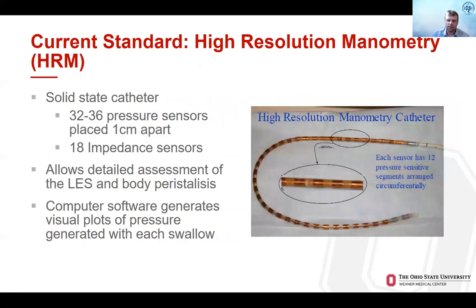More recently, there has been the development of high-resolution solid-state catheters. These catheters have 32 to 36 pressure sensors close together, about a centimeter apart, and 18 impedance sensors along the catheter. This allows a much more detailed assessment both of the LES and of peristalsis. When coupled with computer software, you can generate pictures of each swallow and composite pictures of all the swallows together to give a sense of what is going on when patients swallow.